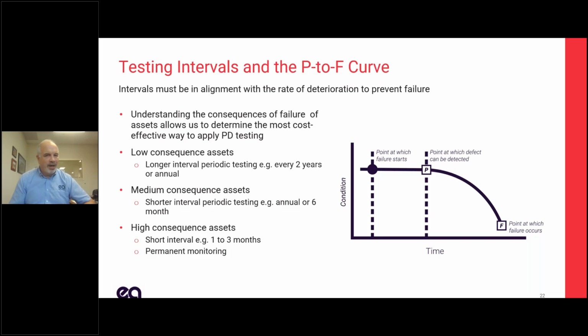What's my environment? If I'm in a high salt humidity environment, it's going to happen a lot faster. And I need to schedule my testing frequently enough that I've got some time between detection and catastrophic failure. If it's a low consequence asset where you've got lots of redundancy, every 2 years is kind of typical. At the other end of the scale, I've got something major. I'm going to lose 100 megawatts of data center floor if I don't do something. I'm recording high PD, I need to detect that, and maybe I need to put in full-time monitoring to make sure I know what's going on with those cables. So it's a decision based on risk-reward.